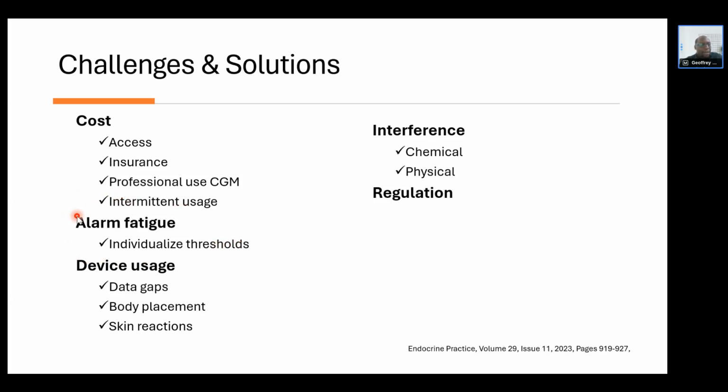There's an issue about alarm fatigue, and we have actually experienced this with our patients: too many alarms can kill people's motivation to use the equipment. So again, you have to individualize these thresholds, especially your predictive thresholds. You really need to have a discussion with your patient.